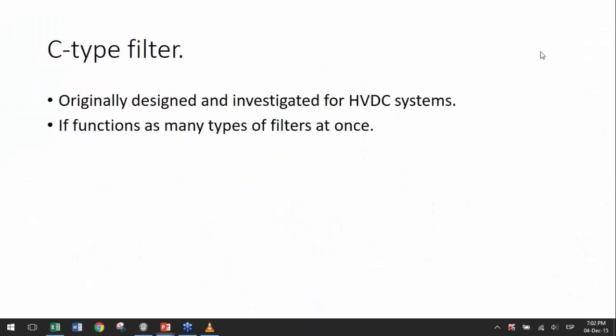So the C-type filter was a filter that was originally designed for HVDC systems. Now, this is not new. This is at least 30 or 40 years old, but it's not so common to hear about C-type filters. The thing about the C-type filter is that it functions as many types of filters at once, and I'm going to show you why in just a few slides. HVDC systems, because of how the power electronics work, tend to produce a lot of harmonics on both sides, on the AC and the DC. So many filters are required to provide good power quality on the system. And as it turns out, this type of filter works great for electric arc furnace facilities because of the implied harmonics.